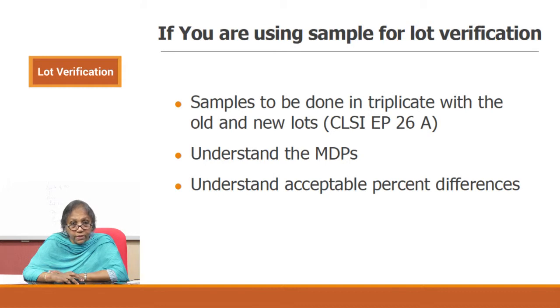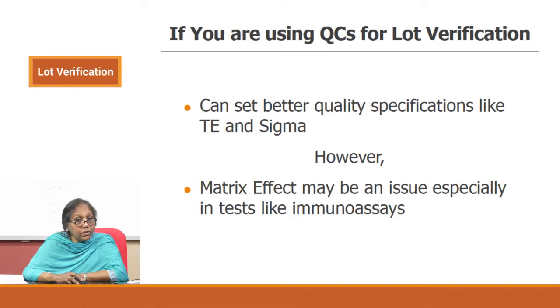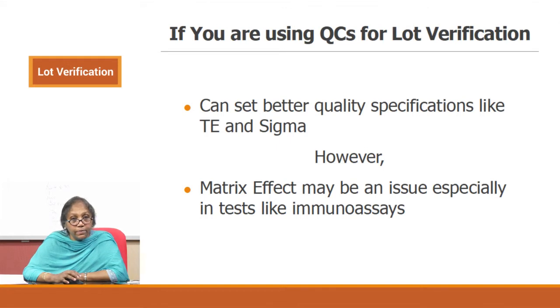If you do the exercise and put in the values, you will get your results. If you are using a QC for lot verification, you can set better quality specifications like TE and sigma. However, matrix effect may be an issue, especially with tests like immunoassays.